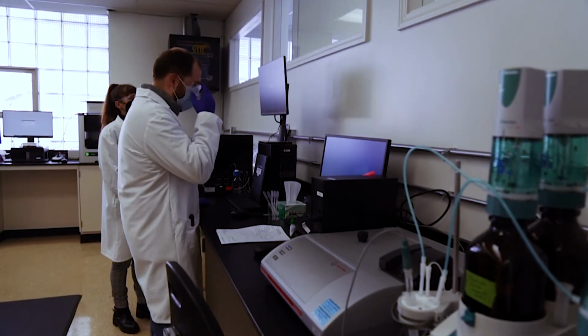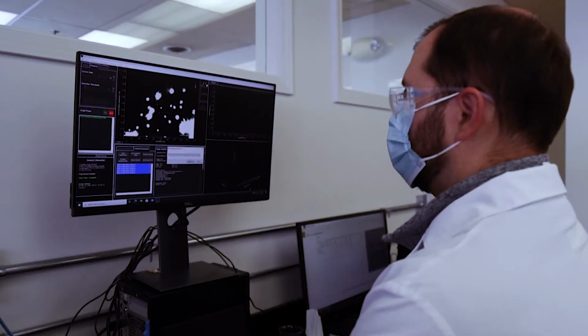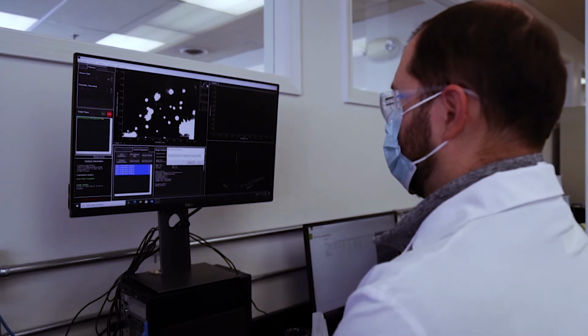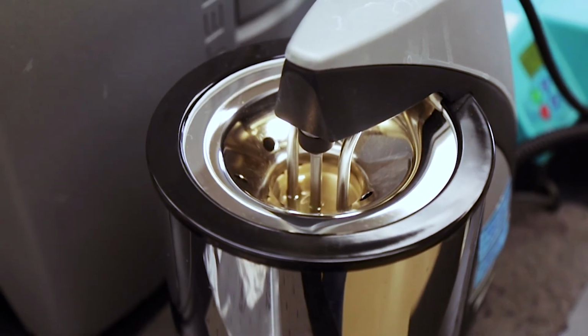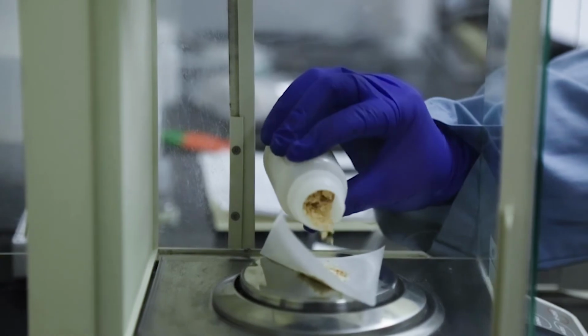And then outside of that, it's often bookended by either accuracy testing, which is a way to demonstrate that the instrument is primed appropriately for the sample. And then beyond that, there's robustness testing, which is mainly for when you want to take a test method and, maybe beyond just its precision, demonstrate that it can uphold analytical variations such as stir setting on an instrument or a sample weight, that sort of thing. So the validation comes together as a full package of these different angles demonstrating a method is strong, essentially.